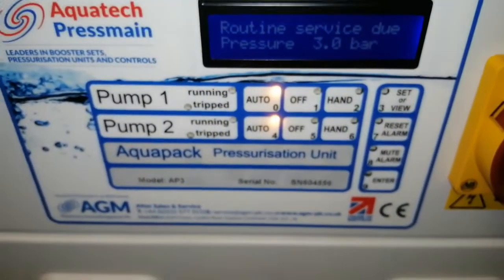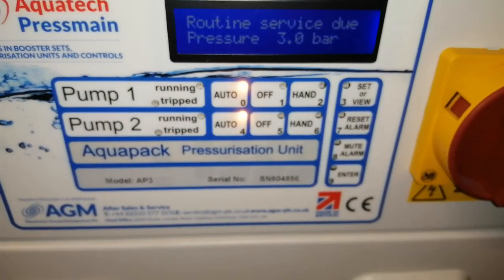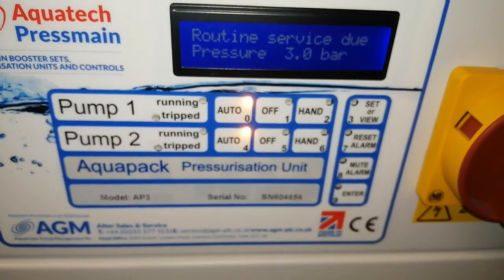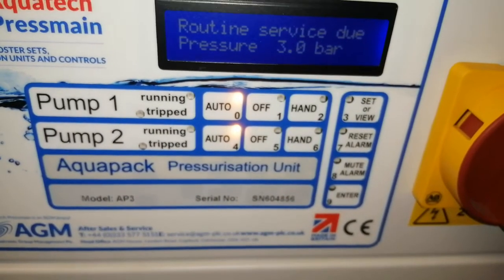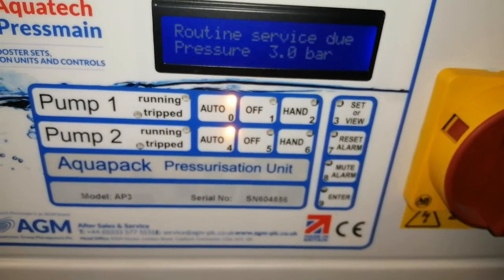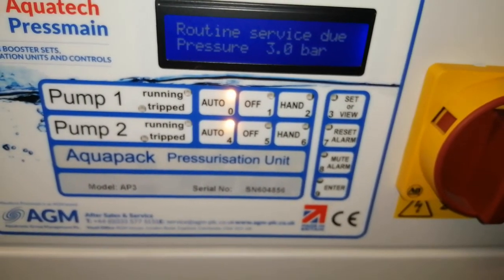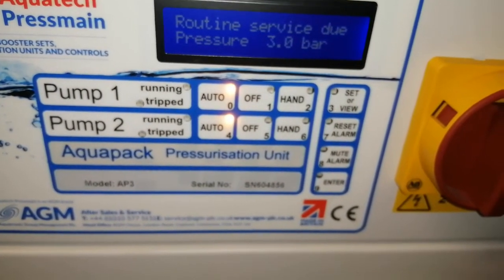When you get on site, check standard stuff such as the pressurization unit pressure, what you have before you start your work, and also check your temperatures as well. Monitor your temperatures when you're turning off any boilers. On this particular site, I don't see any temperature gauges for my flow and return, but on my BMS I may have some temperatures there. But it's good to see so that you're not disrupting any services if possible whilst carrying out your work.